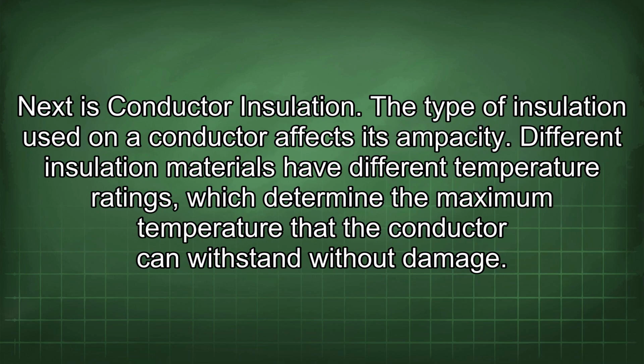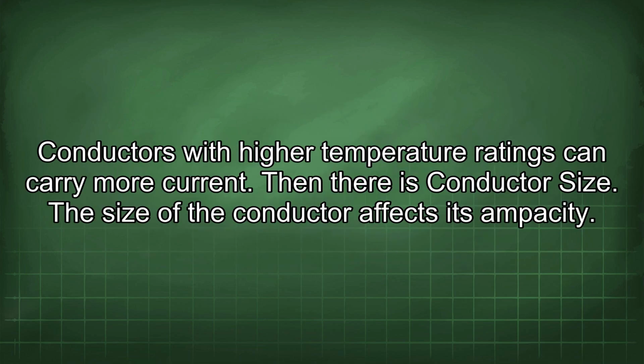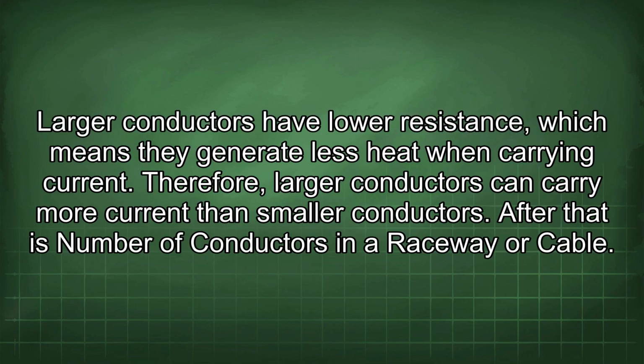Next is conductor insulation. The type of insulation used on a conductor affects its ampacity. Different insulation materials have different temperature ratings which determine the maximum temperature that the conductor can withstand without damage. Conductors with higher temperature ratings can carry more current. Then there is conductor size. The size of the conductor affects its ampacity. Larger conductors have lower resistance, which means they generate less heat when carrying current. Therefore, larger conductors can carry more current than smaller conductors.